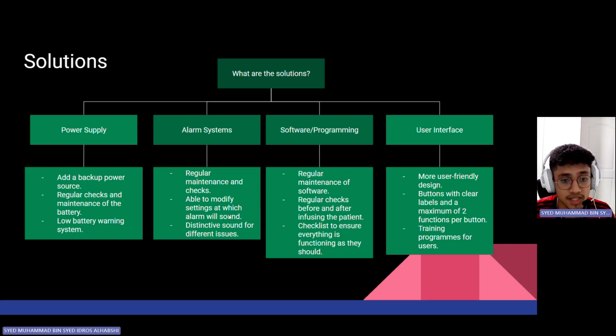They should also be able to modify settings at which the alarm will sound. For example, if the user wants the alarm to sound when there's a specific dosage of the liquid administered already, this should be possible as it will actually help the user to constantly check whether the fluid has been delivered to the patient. Lastly, there should be distinctive sound for different issues. For example, occlusions and air inline should have distinctive sounds so that depending on the sound, users can take immediate action without having to worry about what is the issue. They already know based on what the sound is.